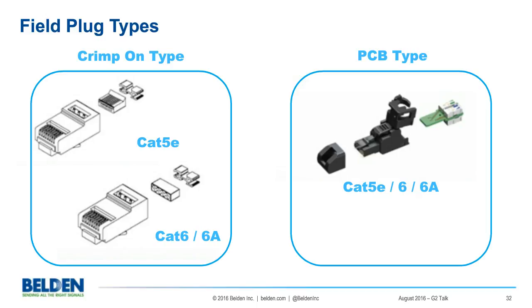The other type is a PC board type. This has a PC board on the inside, and the back end is an IDC, or insulation displacement contact, which pierces through the jacketing and insulation of the conductors, and then makes the connection to the PC board in that fashion.